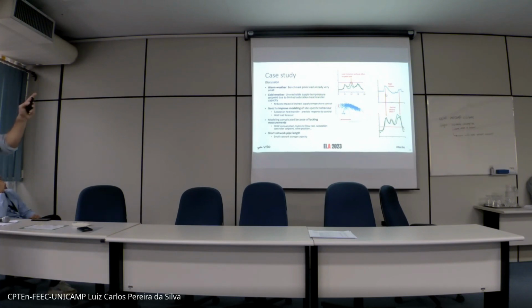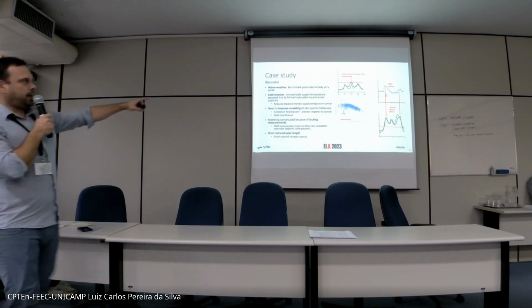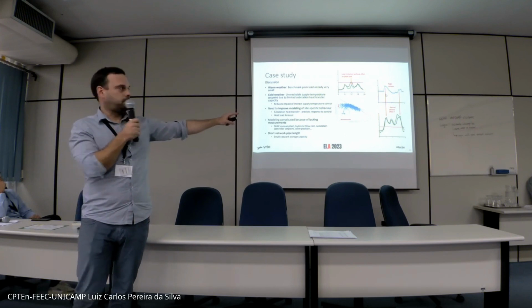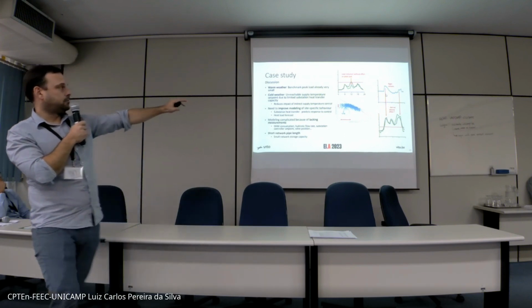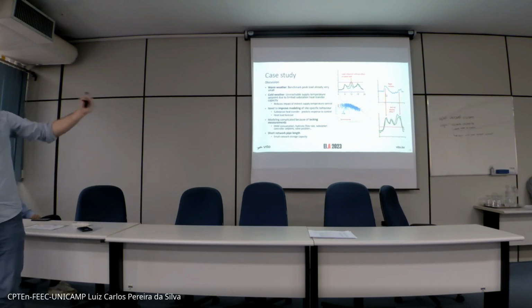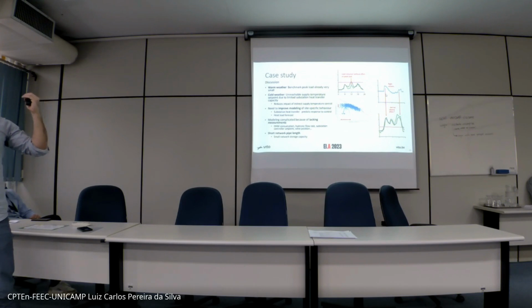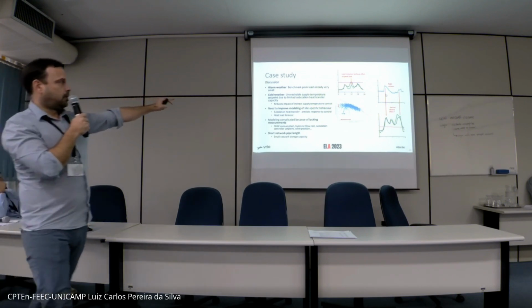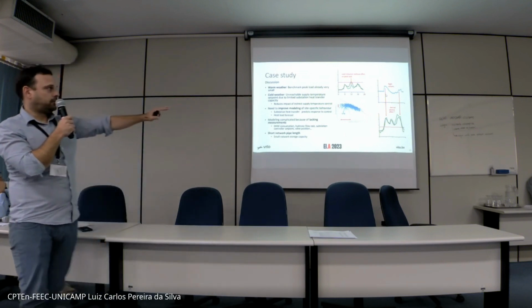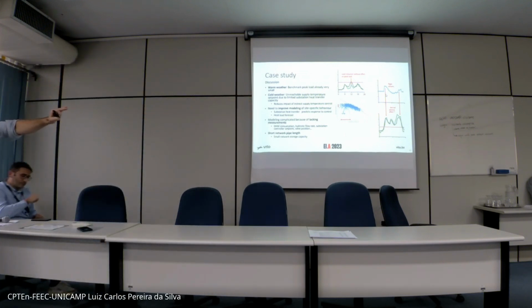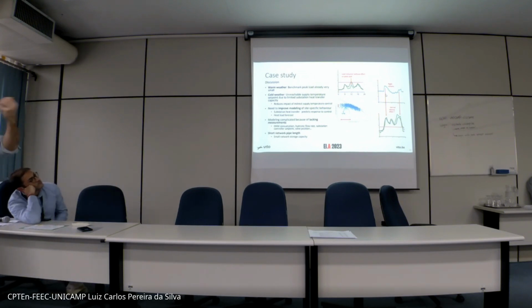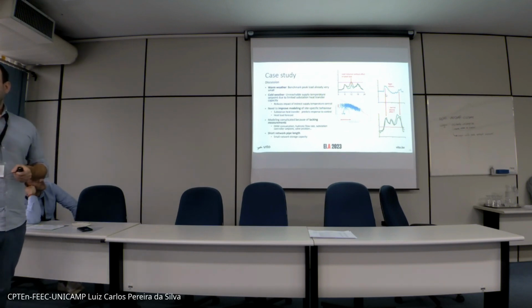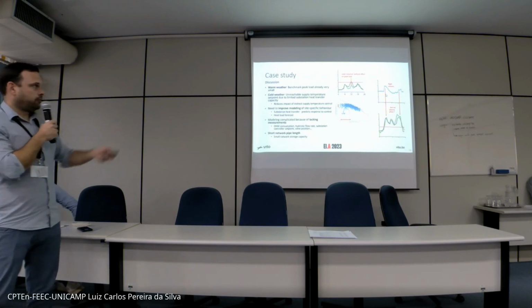But more importantly, during cold weather, we noticed that the substation didn't reach its set point. That's this graph with the blue dots, the actual measurement of the supply temperature going into the heating circuit, while the black line is the set point. You see that in these cold periods, the substation cannot reach its set point, and because it doesn't reach it, playing with the set point doesn't make much difference. We did not account for this effect in the modeling of our substation, so that's something we learned looking into the data.